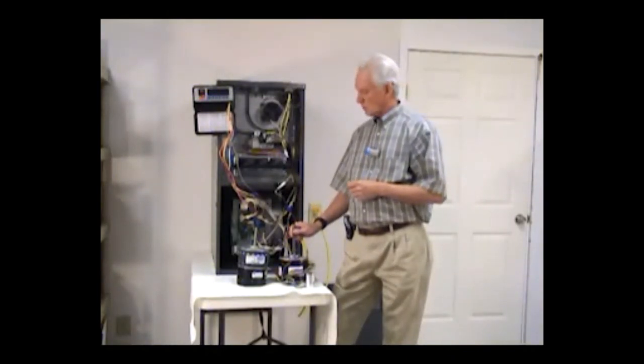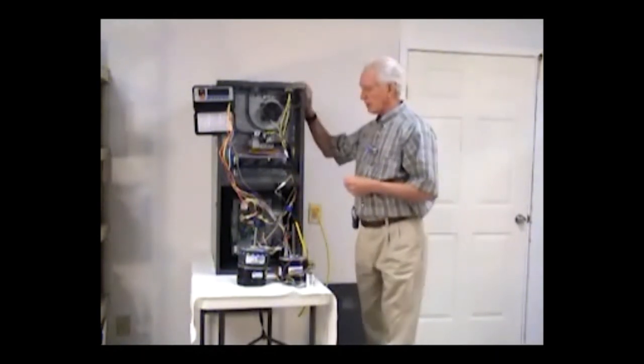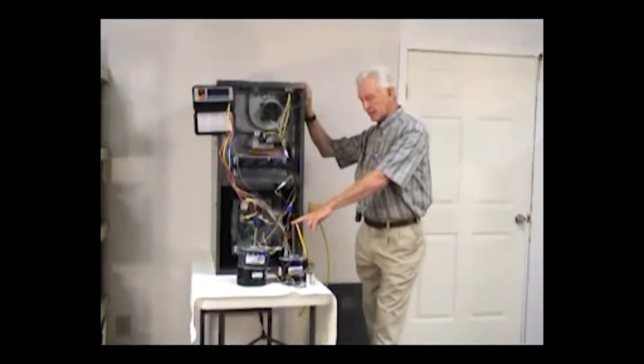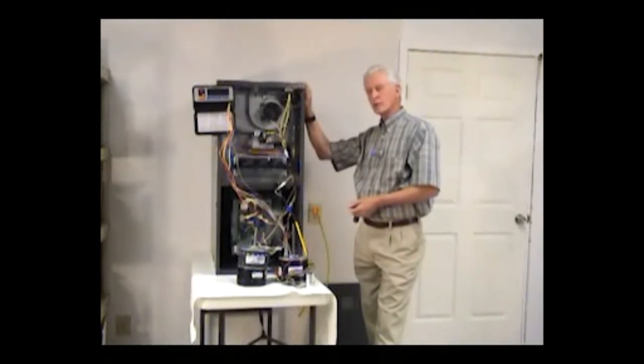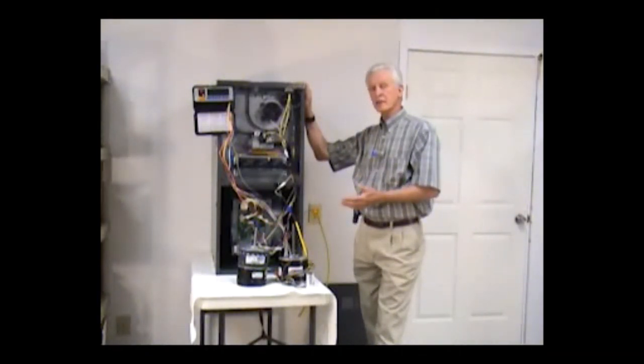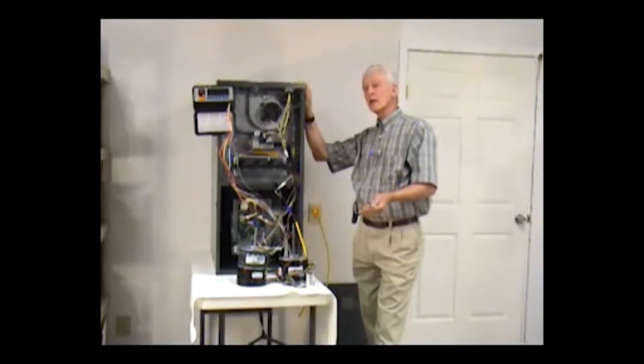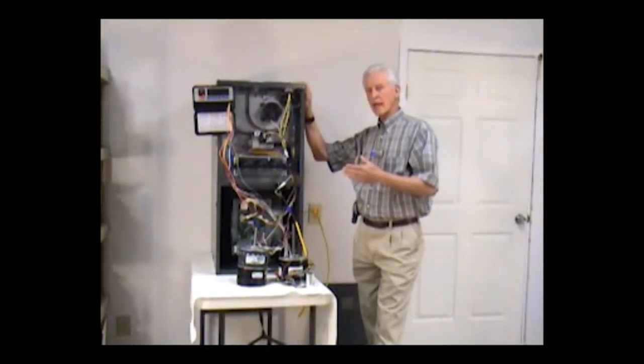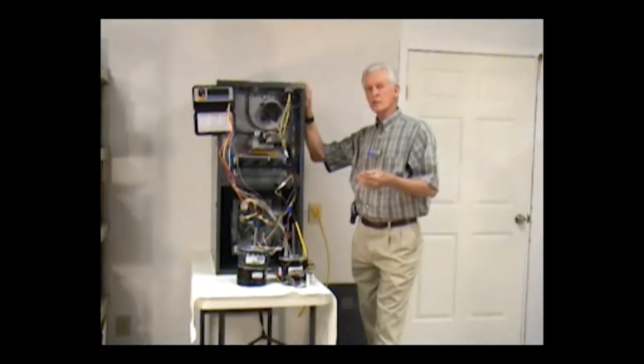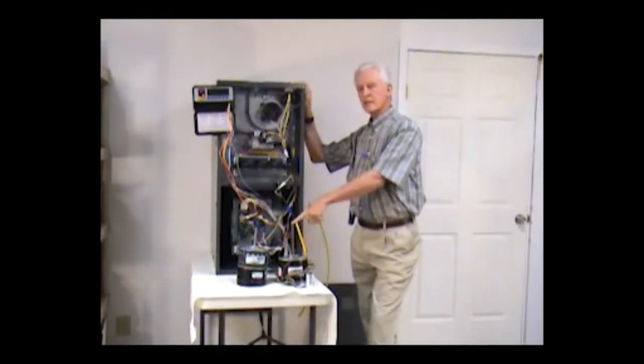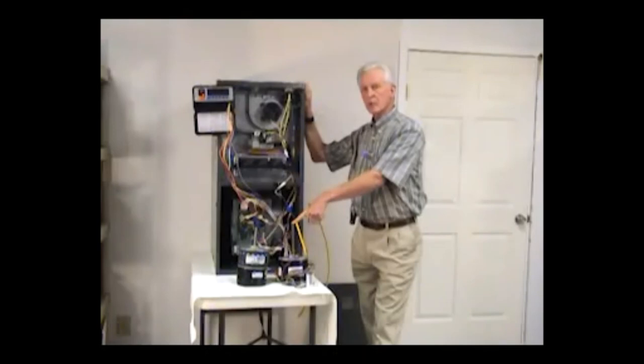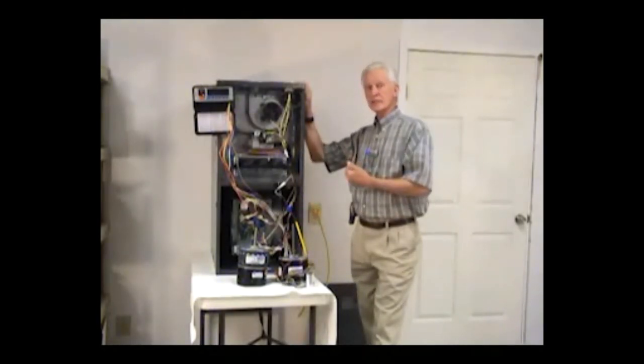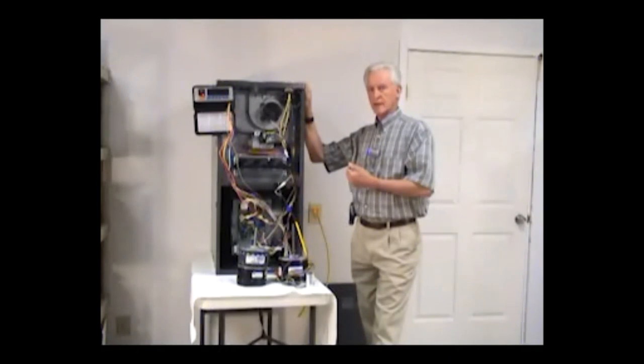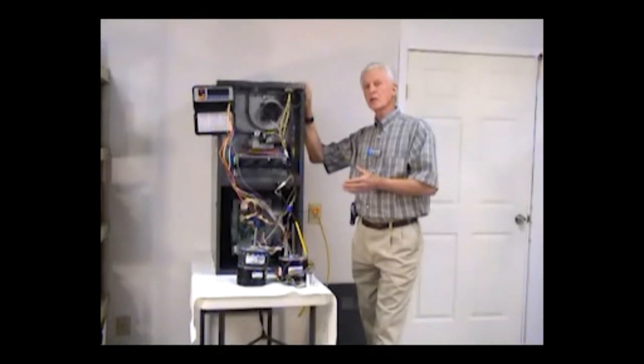Okay, so we can see that if we put a lot of load against this motor, if we want to call that load, that motor is going to produce less and less CFM of air. Where the actual amperage draw goes up is when we have less external static pressure. If we're at 0.2 or 0.3, you would see a slight increase of amperage draw on this motor right here. It then is beginning to give you more and more CFM of air, for the simple reason that we actually, in that case, are really putting more of a load on the motor.